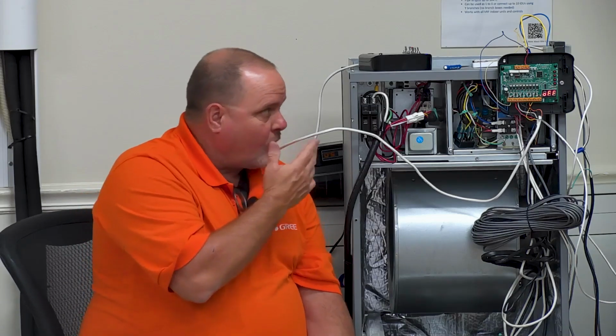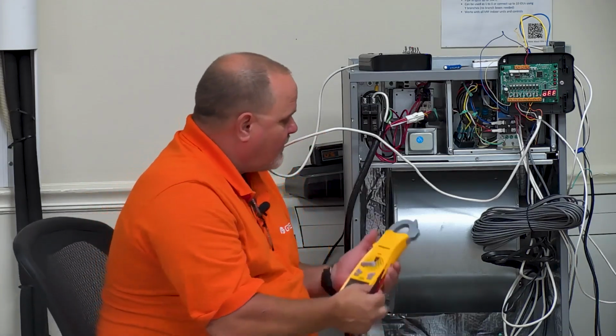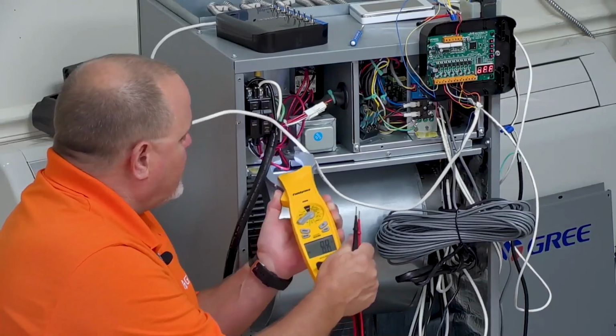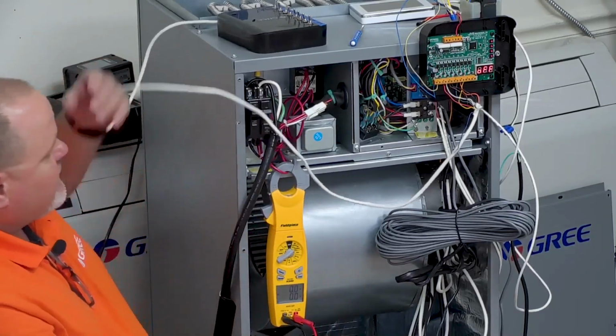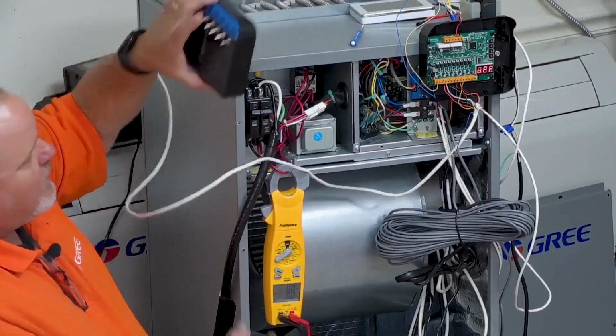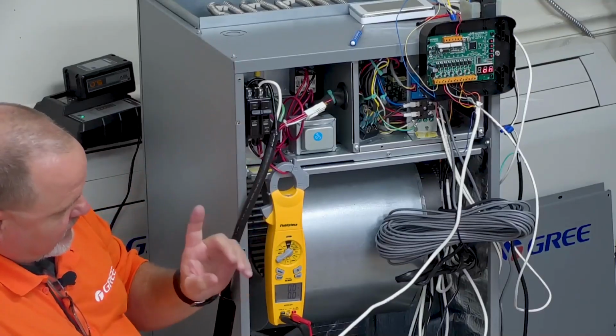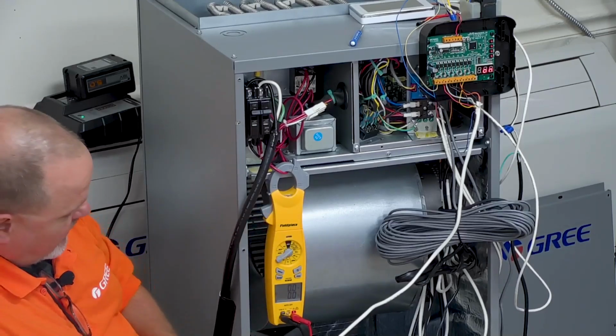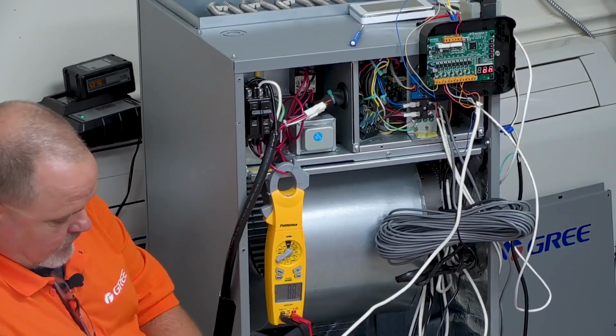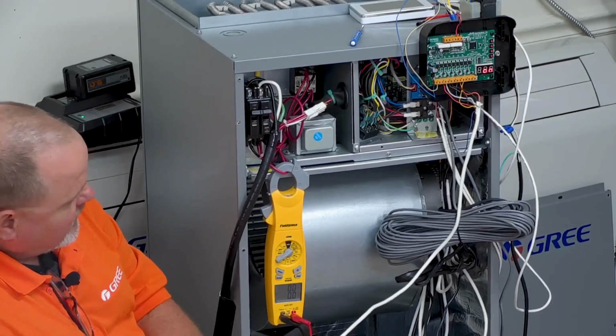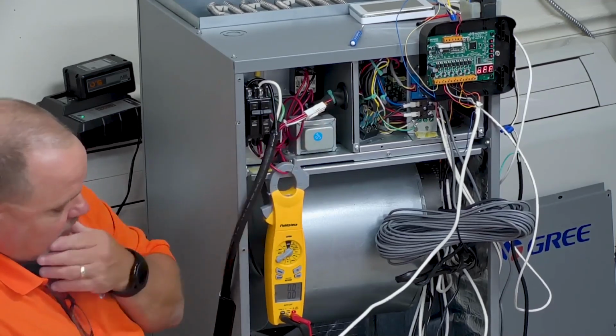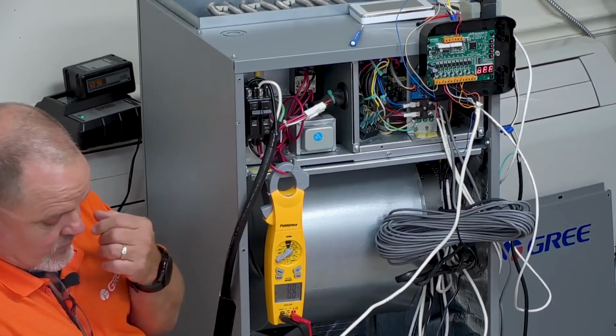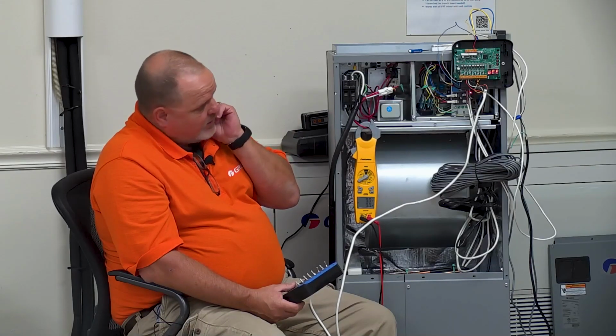Okay? So, as you can see, I energized the reversing valve on this, and I have no operation because it's set up to run in heat pump heating mode. So now, if I give it a Y call and a G call, now it'll actually come on. And I'm not going to leave it on because that unit's coming on over there, and I don't have any refrigerant lines hooked up. So we're going to shut that right back off. Then shut our fan back off. We went back to off. So now it is going to have a little bit of a delay here.